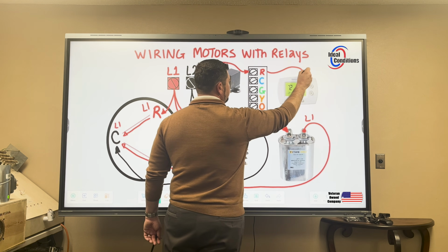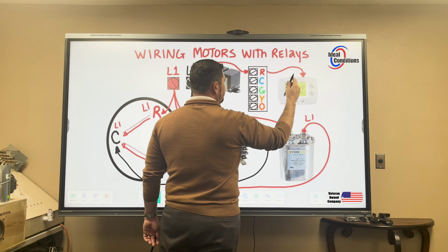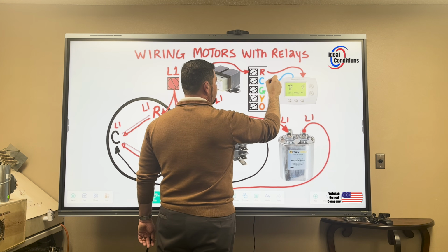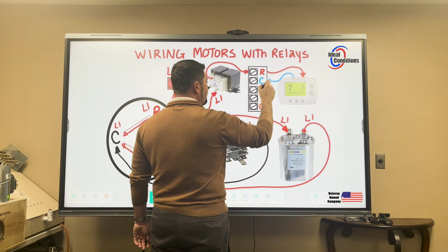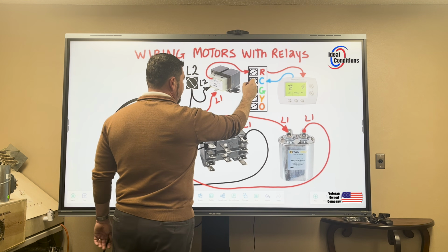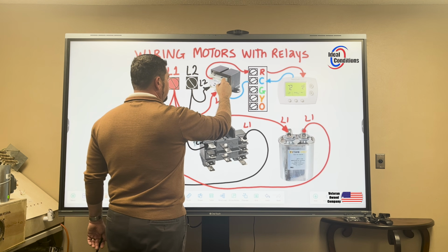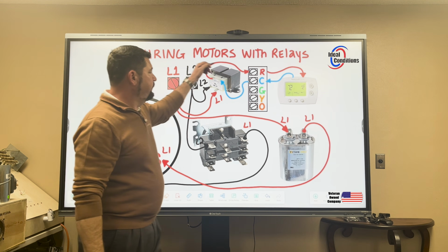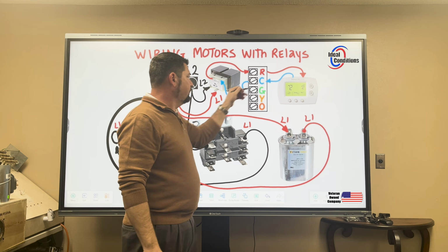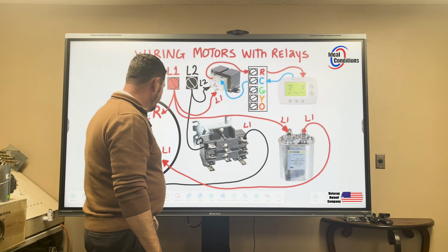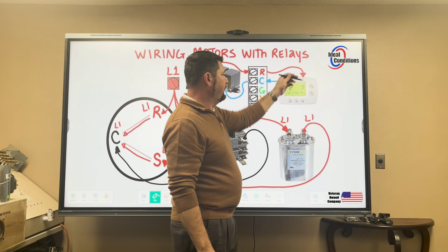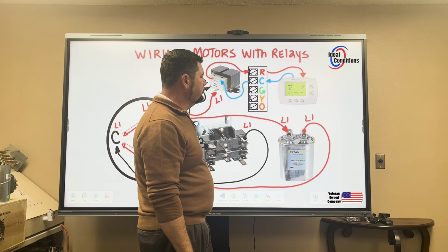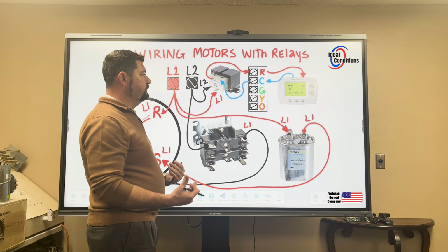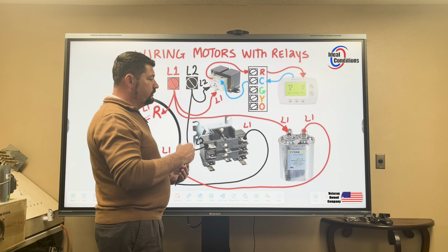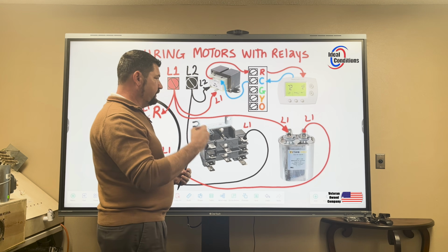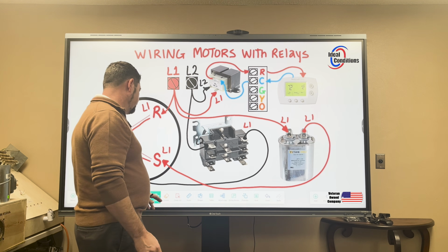Coming out of here, we're going to give the thermostat 24 volts. And then for us to have a display, if we're not using any kind of DC voltage like batteries provide, we're going to have to provide a path back to the transformer. And with this, I've created a loop or a path back to the transformer, and now I can have a display. The thermostat is going to take this 24 volts and relay it over to all the respective terminals that has been designed or programmed to put power on, whether it's in heat mode, cool mode, or just the fan in the on position.